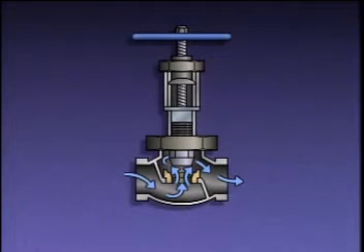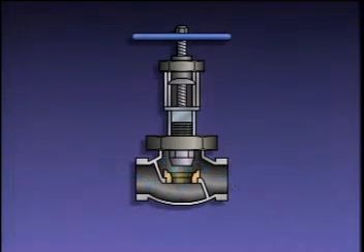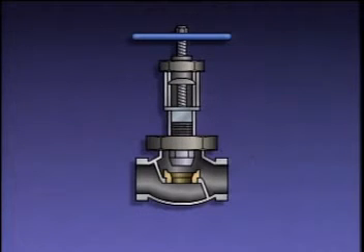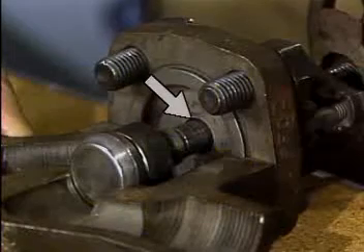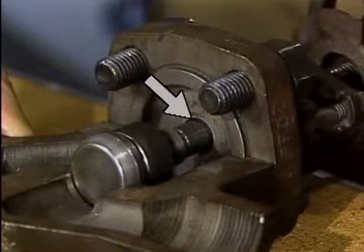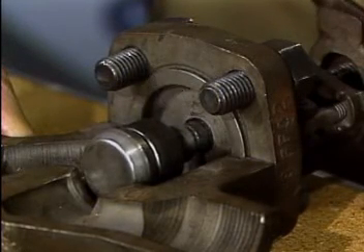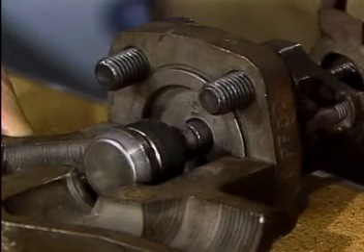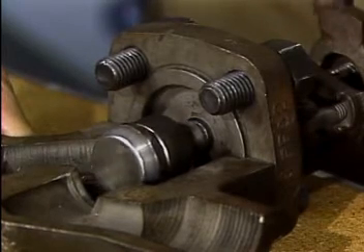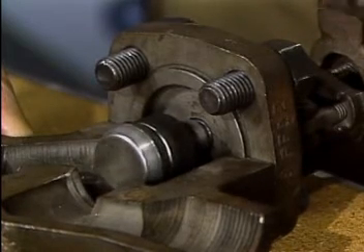This design feature prevents uneven wear of the seat and disc. In addition to the regular seat, some globe valves, like some other types of valves, have a back seat. If we look inside the bonnet of a globe valve that has a back seat, we can see that when the valve is fully open, the top side of the disc seats against the back seat.